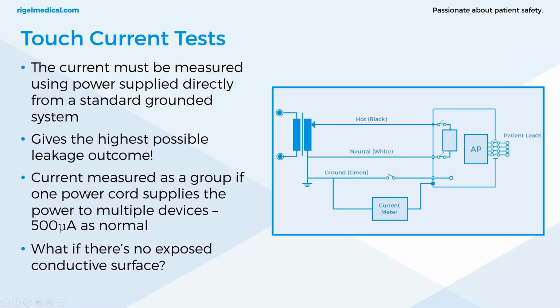Similar to how you would do it with applied parts. If you're testing applied parts and the sum of the leakage is higher than the test limit, then you're just going to break it down into individual applied parts. You're going to do the same thing here. You'll break down each medical device to see where that fault is coming from.